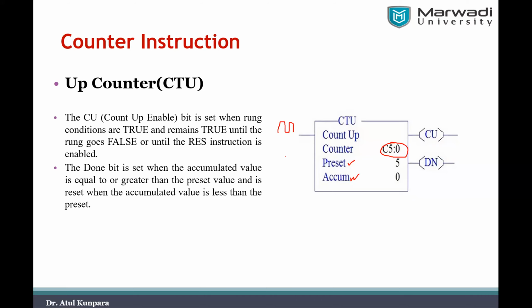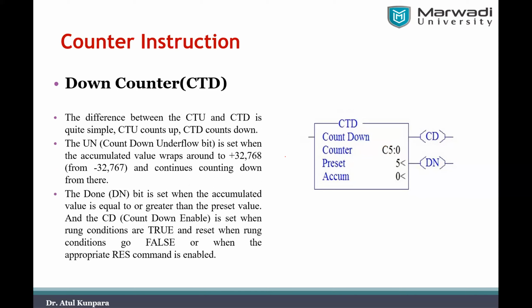Yes, sir. Similar to this up counter, you can have the down counter. In the down counter, you will have the counting task reverse to what you have seen in the up counter. Here also your done bit is going to be on whenever your accumulator value is more than the preset value. But here the operation is a little bit different.